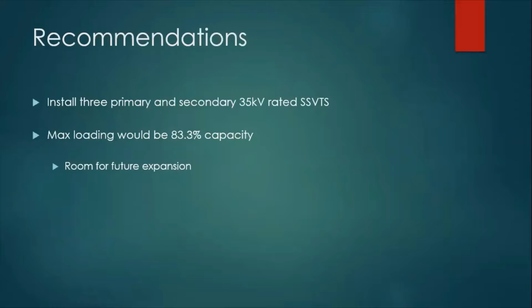With the overall specification that the substation can be easily expanded into future line positions, this accounted for future loads and would still provide additional loading without the need for new SSVTs to be installed during the next phase of the project. The controls design consisted of electrical wiring for AC and DC elements. The AC schematics, which include the one line with relaying and line differentials, show the interactions between equipment CTs and yard CCVTs into the overall protection scheme, while the DC schematics show interactions between the defined relays, lockouts, and the breakers' trip coils.